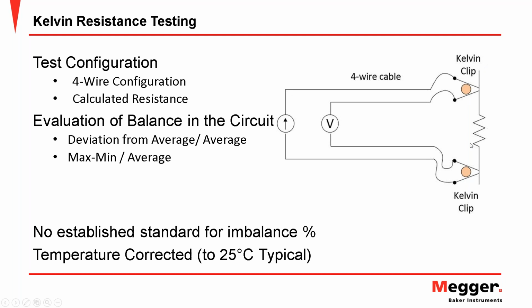But if we do that, then we get a very precise measurement for each phase, and then we can do some evaluation of the balance of that circuit by one of these 2 calculation means, whether we take the full span, the max minus min, or a deviation from the average measurement of the 3 readings that we obtain, all over the average value, to determine the balance of the circuit. Now, unfortunately, there's no established standard for that balance, but we recommend, if you're testing directly at the motor terminals, that balance be less than 3%. In most cases, we expect on the order of 1% or less.